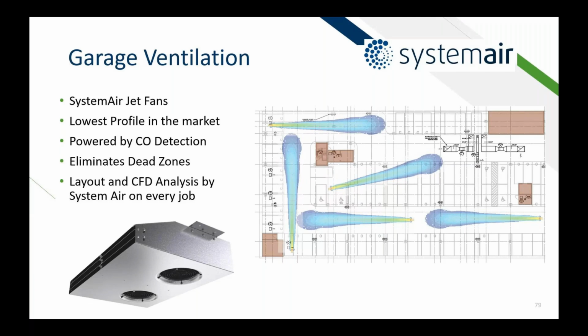They're 6 inches deep. They'll suck in air and blow it across the garage, from the intake to the exhaust. They entrain air throughout, they eliminate the dead zones, and they're all powered by CO detection. One of the best things about this is that all you have to do to get a really good layout involving these jet fans is just send us an area or elevation view, ideally, and we'll get involved with SystemAir, and they'll send you a full layout like the one you see here.